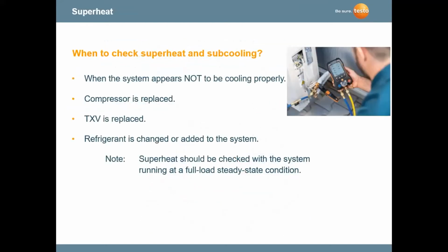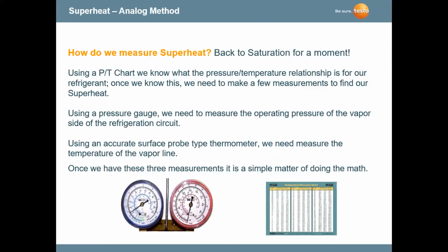Checking superheat. When do we check superheat? Anytime we break into the system. We have a compressor failure, TXV replaced, when the system is not charging or not cooling properly. And anytime refrigerant is changed or added to the system, again, we need to check superheat and subcooling.